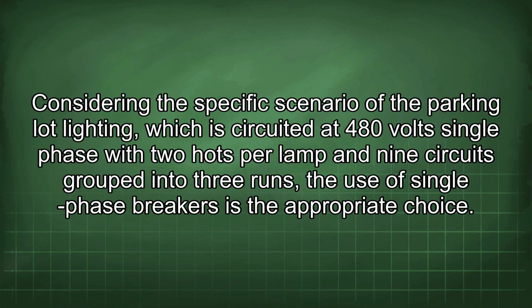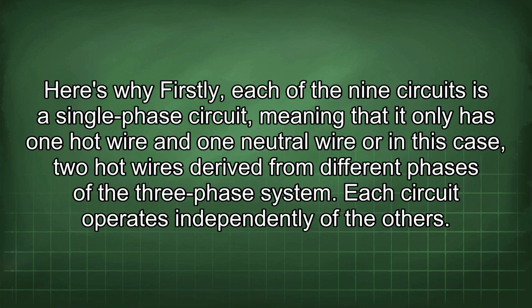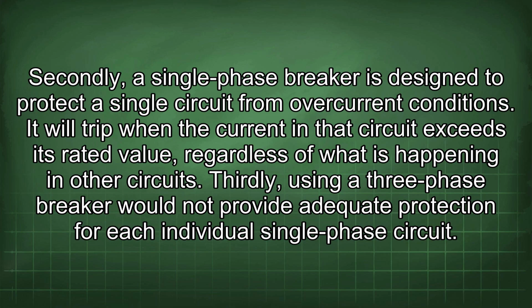Considering the specific scenario of the parking lot lighting, which is circuited at 480 volts single phase with 2 hots per lamp and 9 circuits grouped into 3 runs, the use of single phase breakers is the appropriate choice. Here's why. Firstly, each of the 9 circuits is a single phase circuit, meaning that it only has 1 hot wire and 1 neutral wire, or in this case, 2 hot wires derived from different phases of the 3-phase system. Each circuit operates independently of the others. Secondly, a single-phase breaker is designed to protect a single circuit from overcurrent conditions.